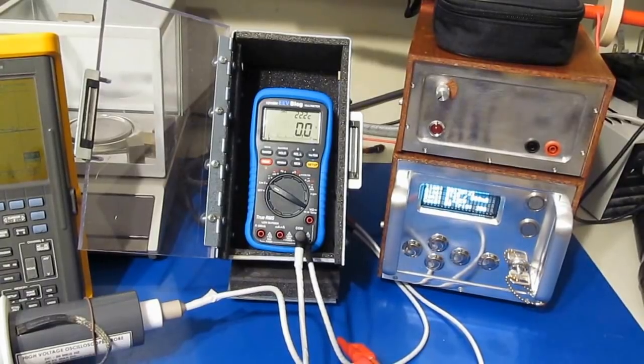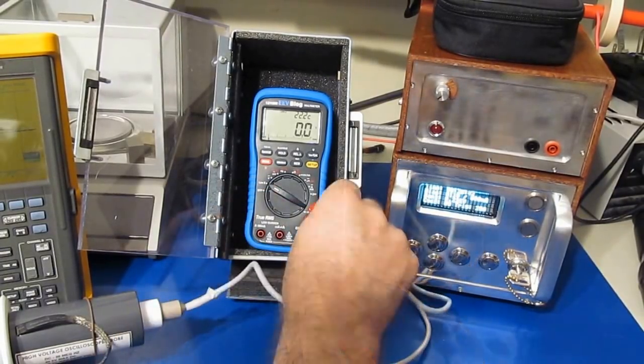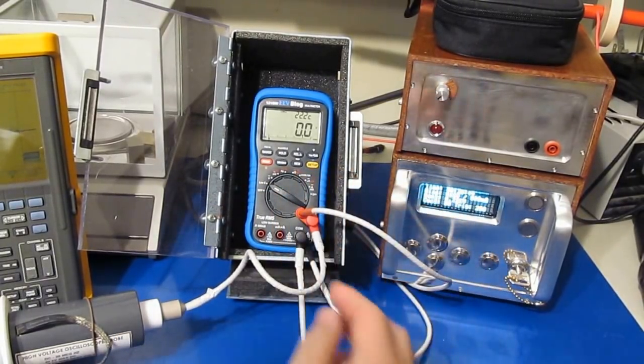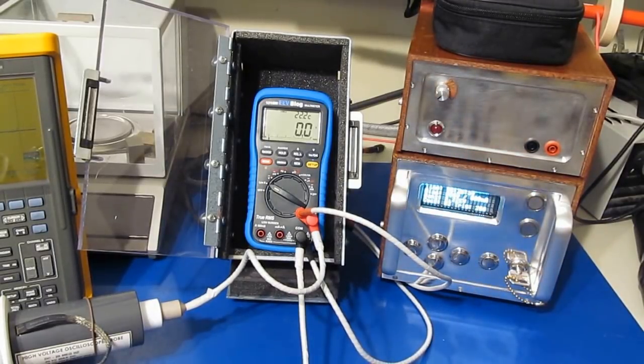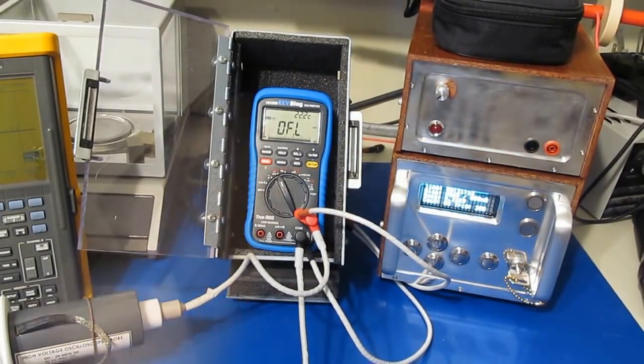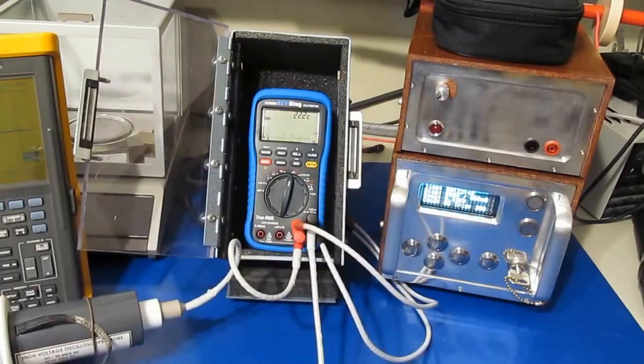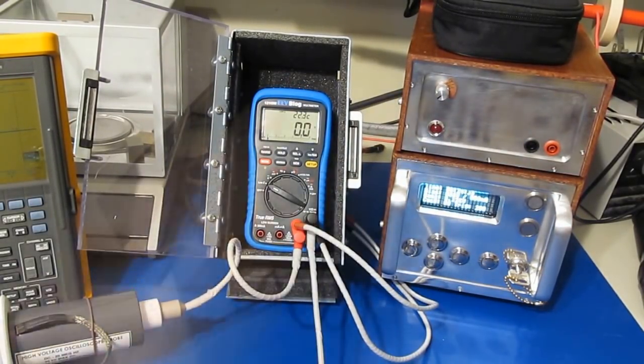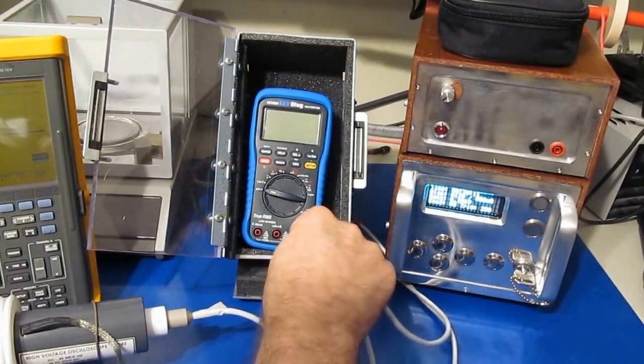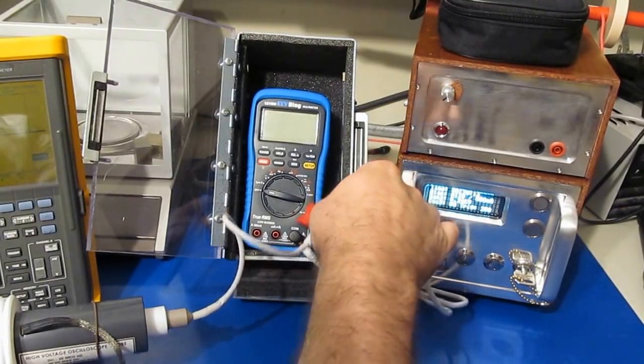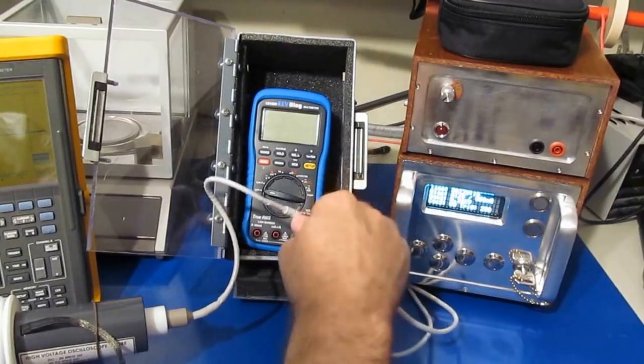We're going to be starting with 1.5 kV. Again, the meter previously had failed at 2 kV. So we'll be applying again 5 transients, positive and negative. Alright, so the meter passed functional just fine. That does not surprise me too much.